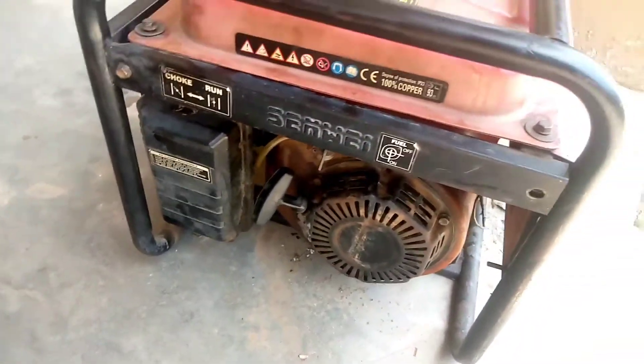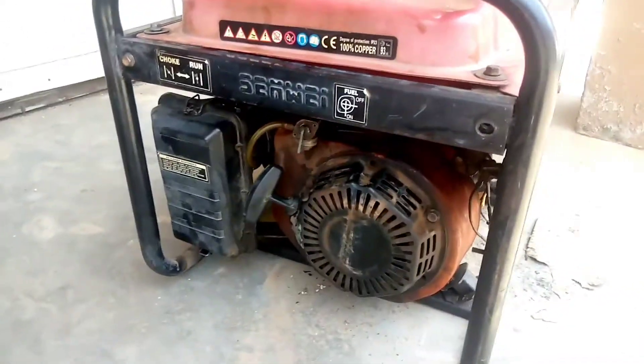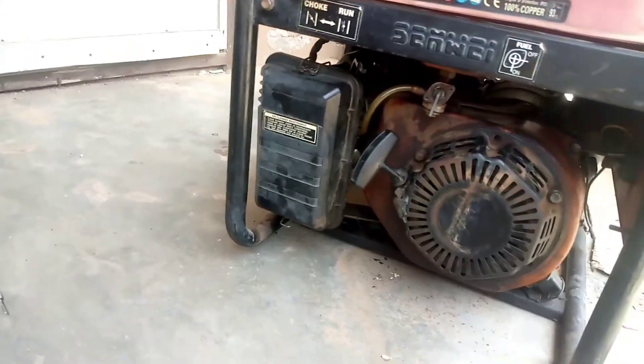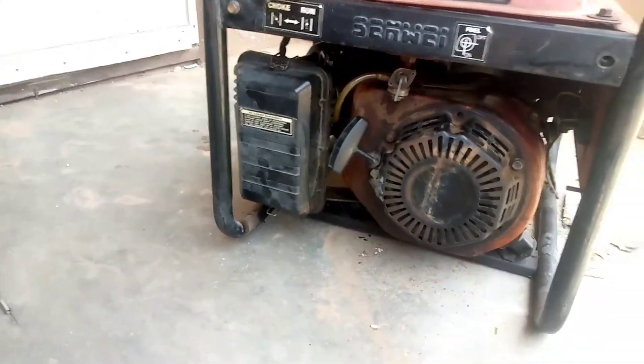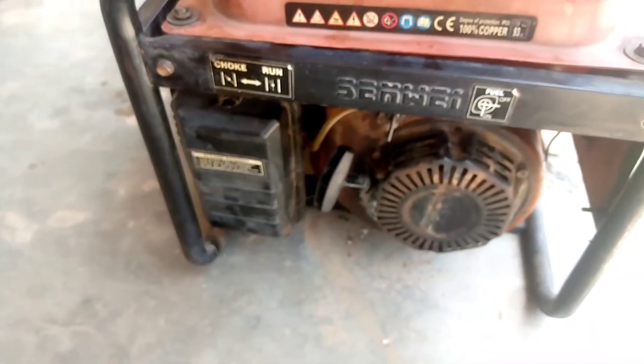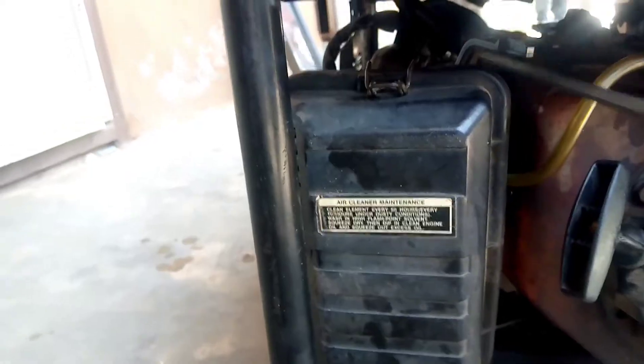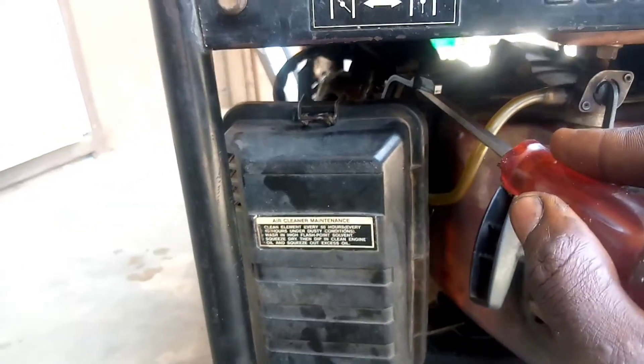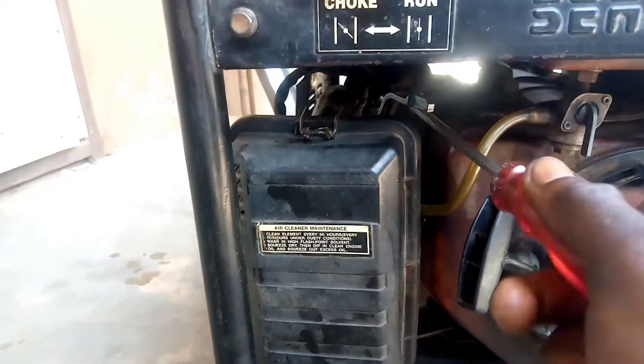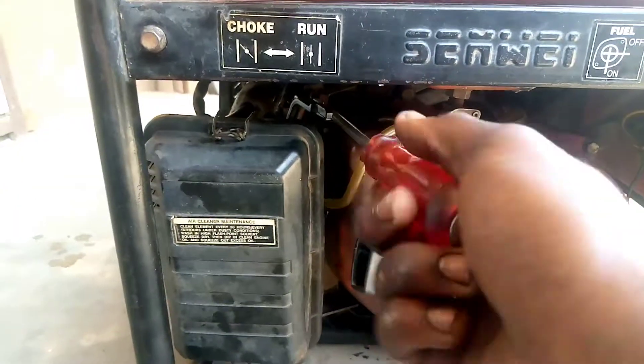We've put up the generator now. What could be the cause of this vibration, the low speed, and the low current? Let's think — we're going to increase the speed a little bit and check it out, whether it's going to change. Let's increase the speed and see.